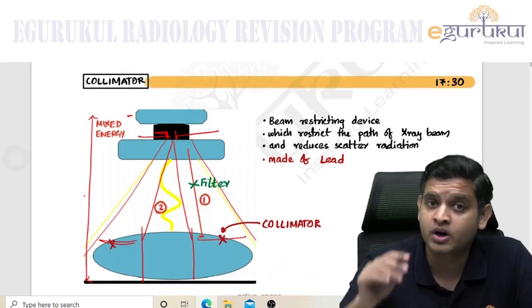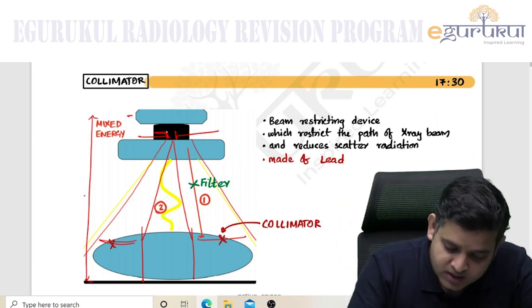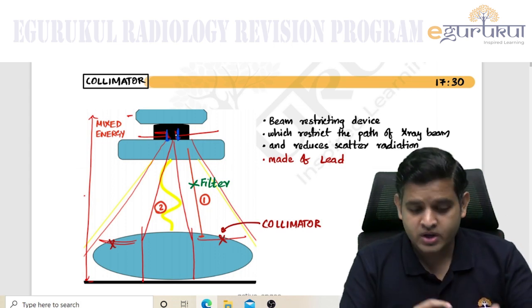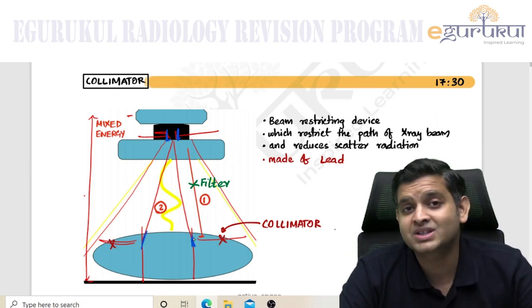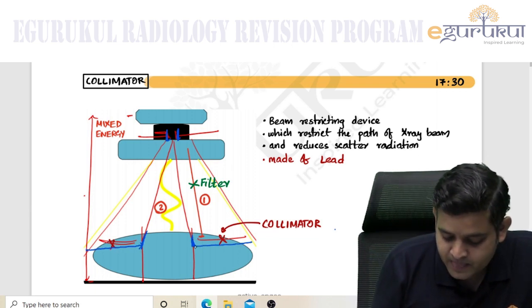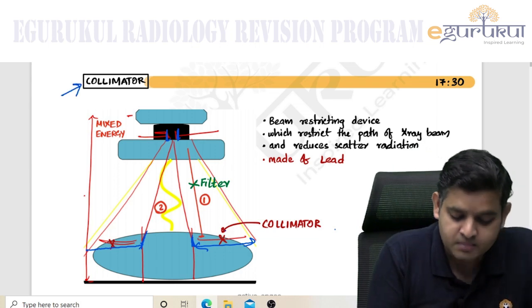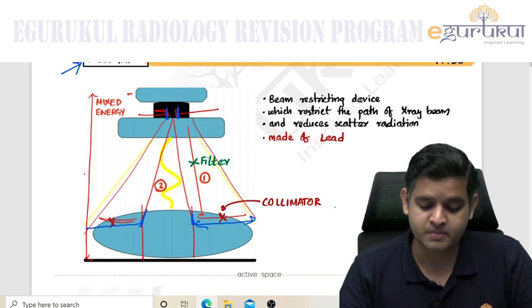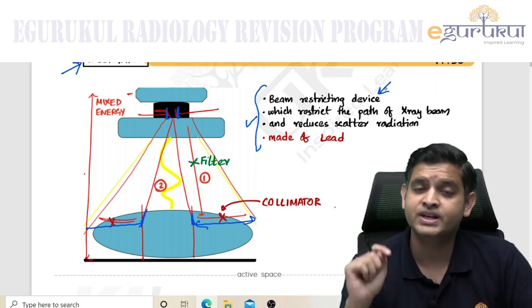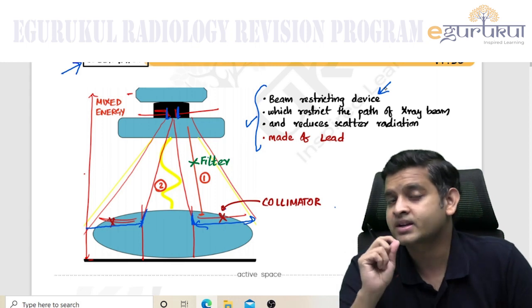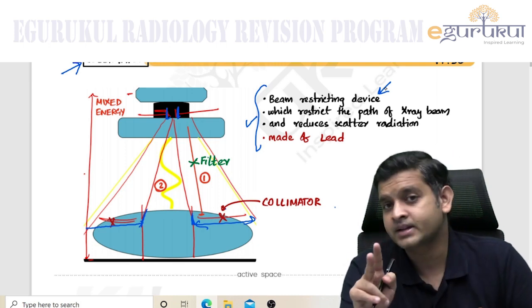Because the beam is diverging, we need a device to restrict its path so that the beam only goes to the part you want to scan. This is done by a collimator. It restricts the path of the beam, thereby decreasing scatter radiation. So the collimator is a beam restricting device which restricts the path of the x-ray beam and thereby reduces scatter radiation.